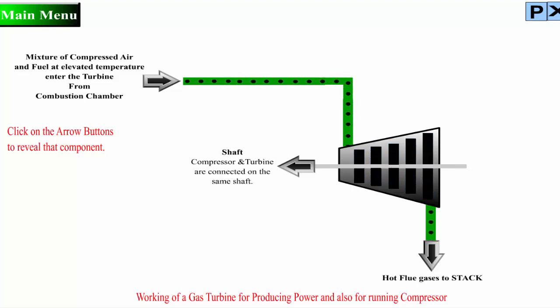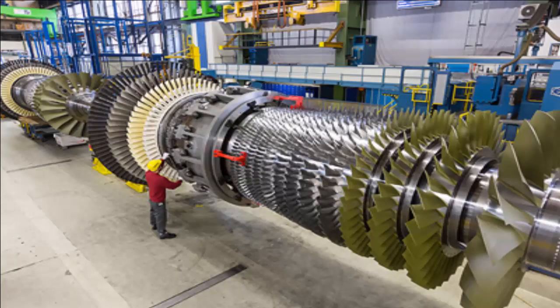Another way to boost efficiency is to install a recuperator or heat recovery steam generator (HRSG) to recover energy from the turbine exhaust. A recuperator captures waste heat in the turbine exhaust system to preheat the compressor discharge air before it enters the combustion chamber. An HRSG generates steam by capturing heat from the turbine exhaust. High-pressure steam from these boilers can be used to generate additional electric power with steam turbines, a configuration called a combined cycle. A simple cycle gas turbine can achieve energy conversion efficiencies ranging between 20 and 35%.